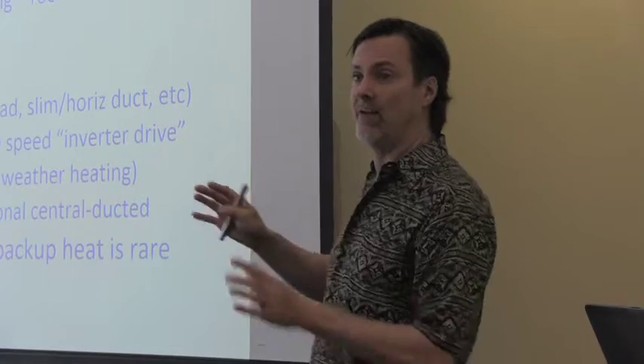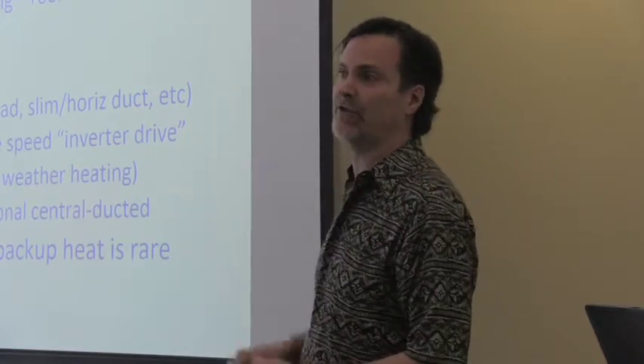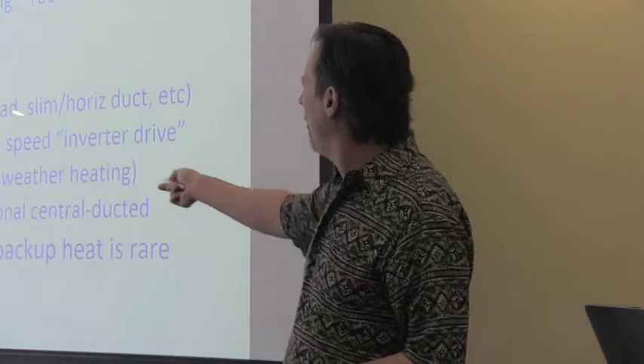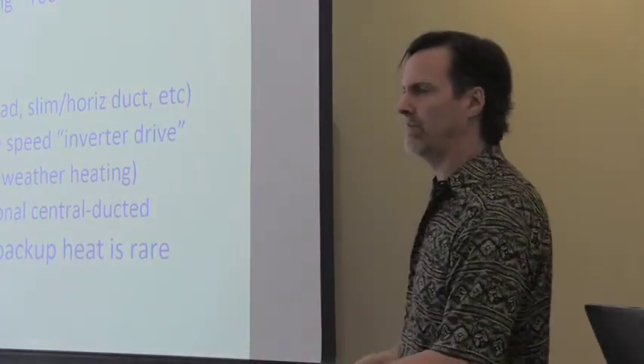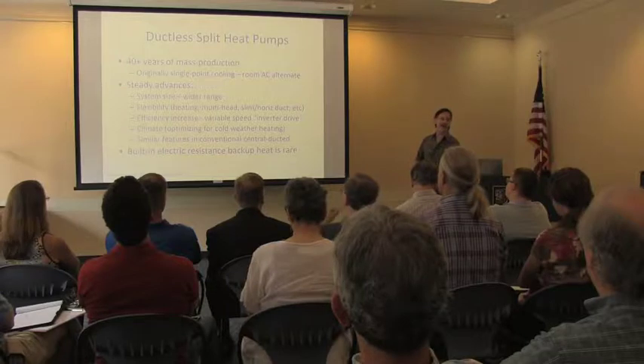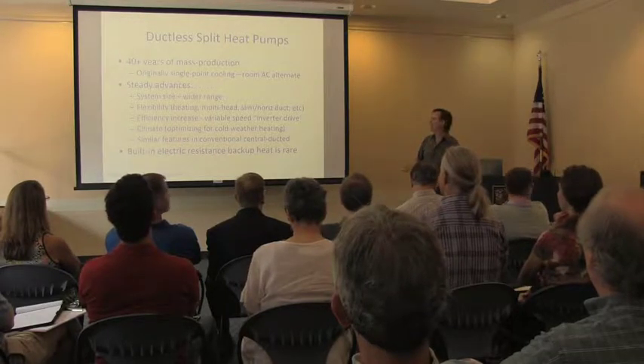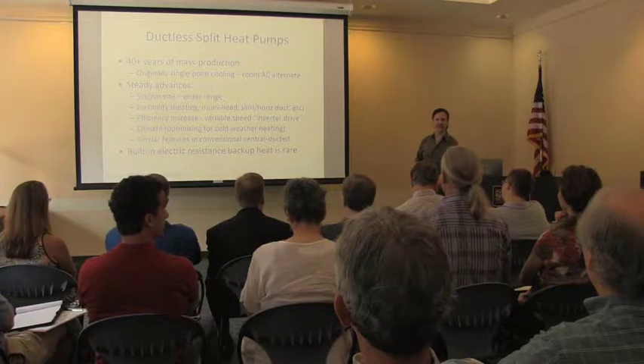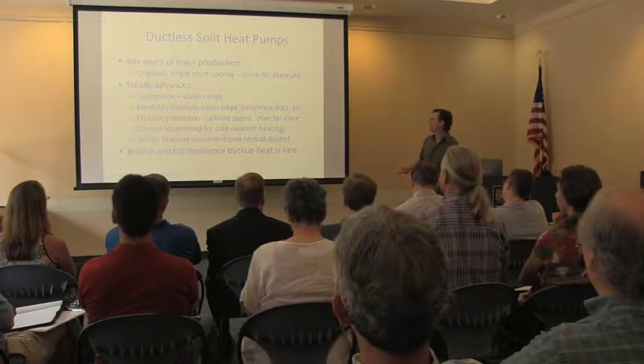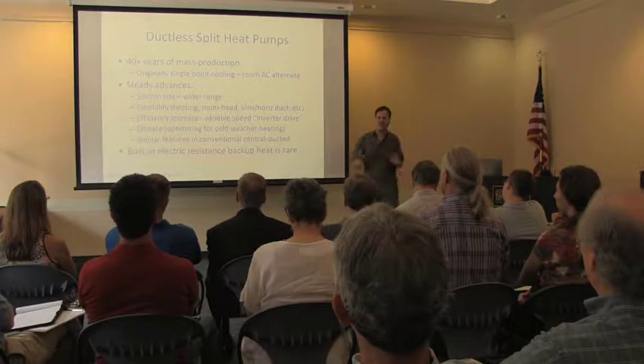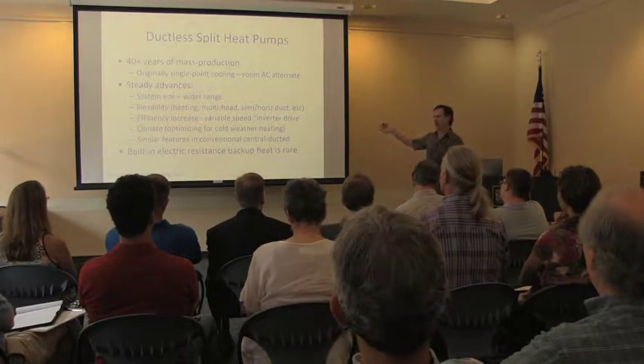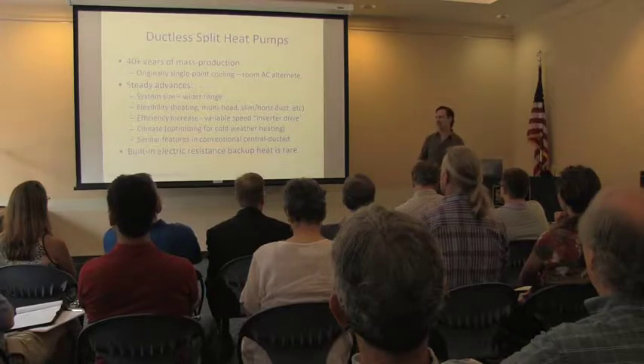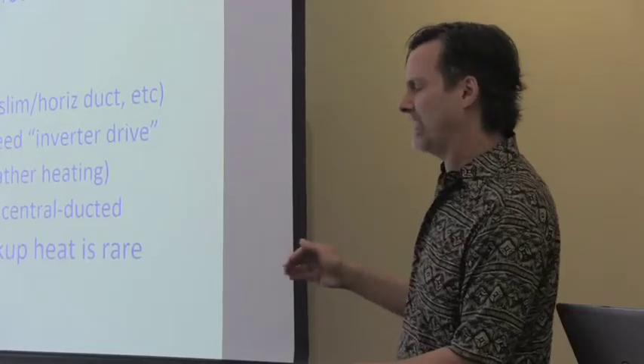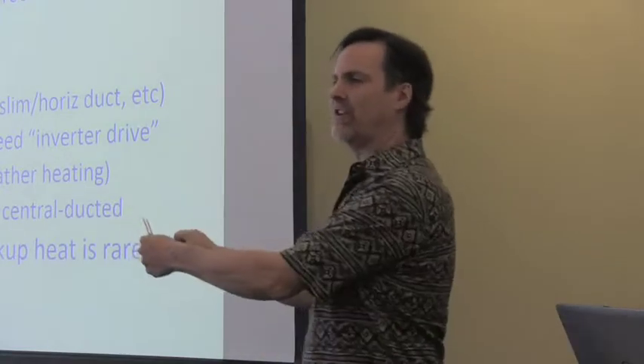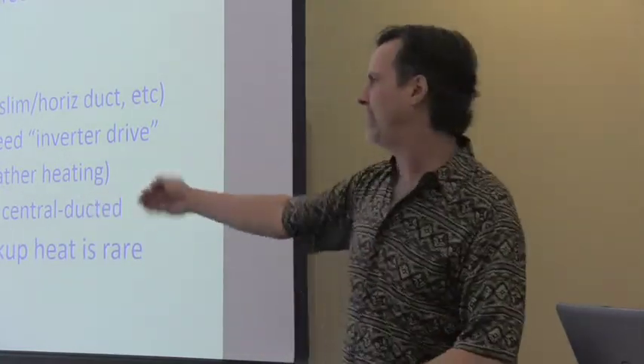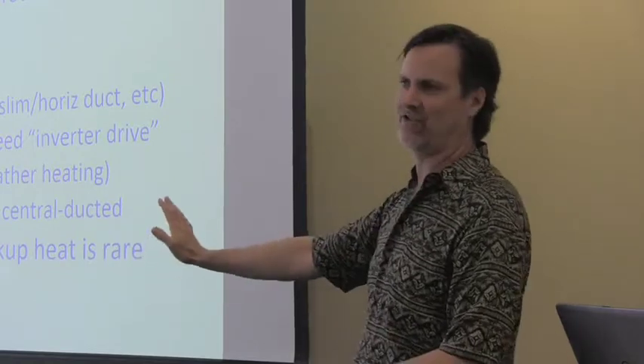And as Jen said, with the high-end ground source heat pumps, they also use variable speed. But not all mini-split heat pumps have variable speed drives, but certainly all of the high-efficiency ones do, and that's quite common. And I'll tell you a little bit in a few minutes about how to find the right equipment for cold climates. It's essentially this variable speed is important if you think about driving your car from point A to point B in the city. It's going to be less efficient if you stomp on the gas and accelerate as fast as possible and drive at 50, 55 miles an hour and then stomp on the brake at the next stoplight.